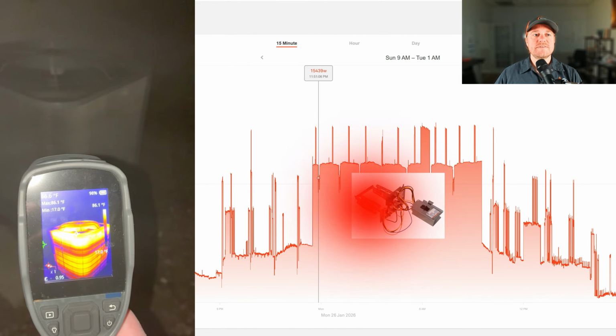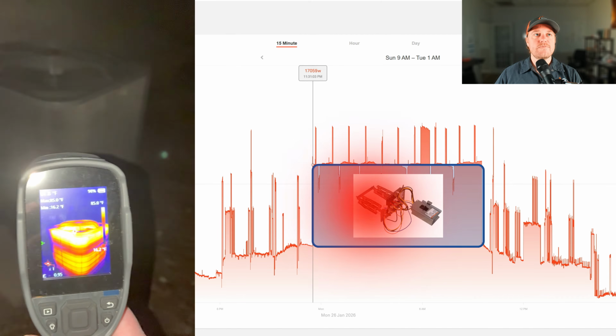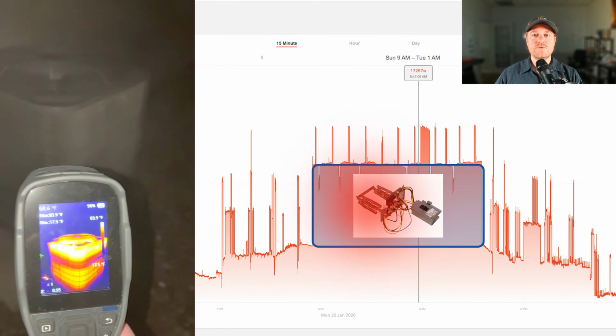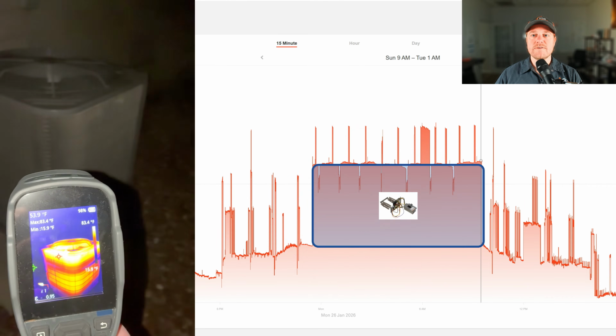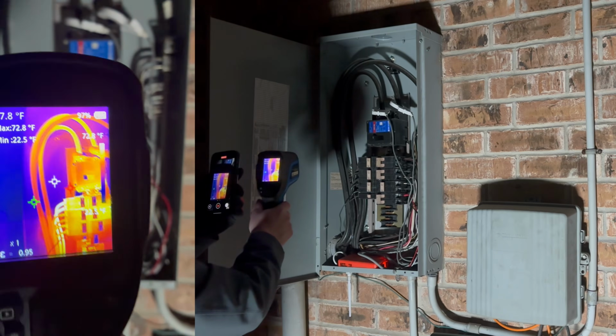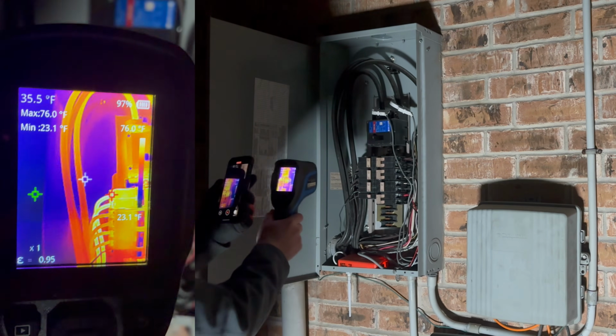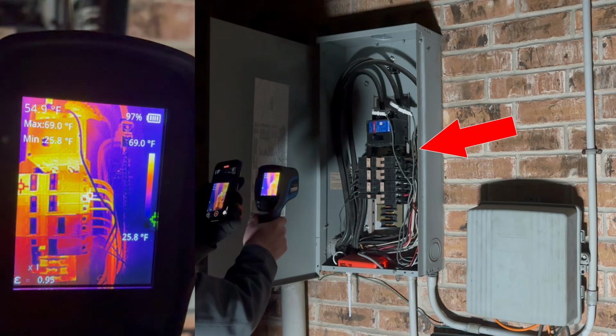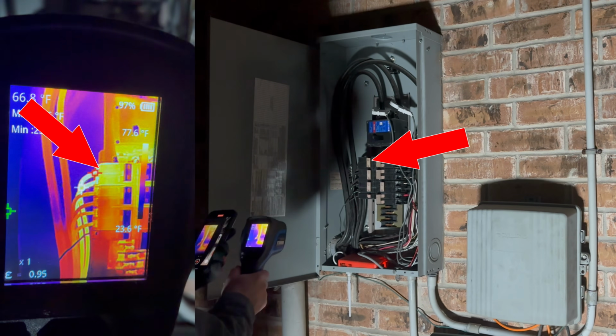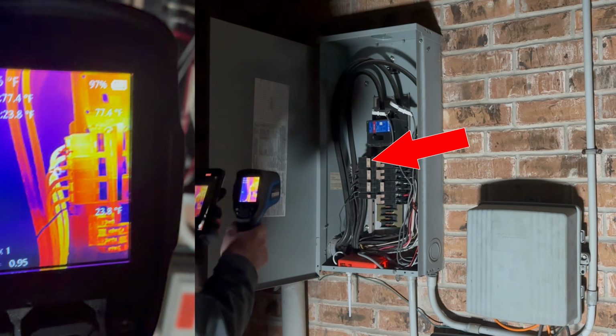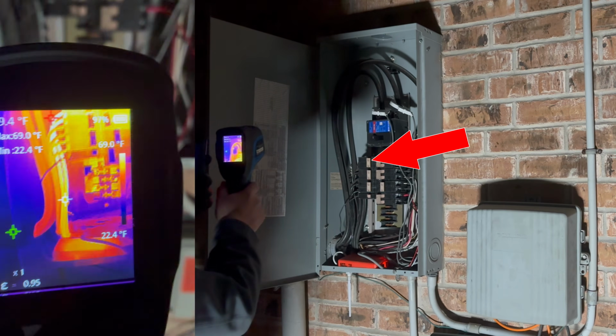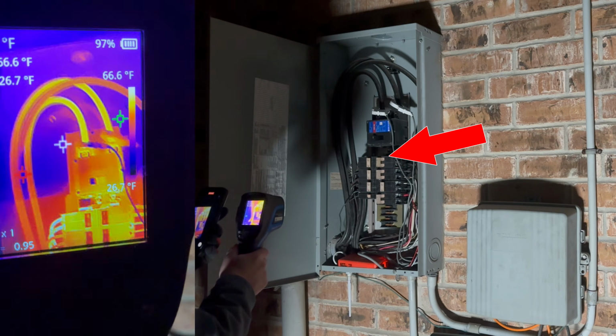However, what we see is the heat strips being used non-stop from 11:30 p.m. to 9:30 a.m. So 10 hours straight. And I was thinking that the circuit that's powering the heat kit is getting a little warm. And you can see it right here. And yep, it sure is. And this is why it's important that the wire is correctly sized, because the smaller the wire, the more heat it's going to generate, which could lead to a fire.